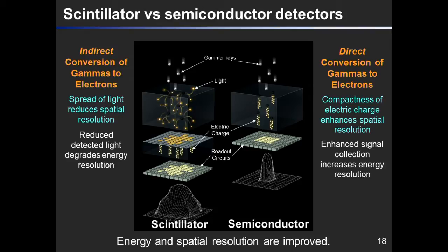On one surface of the scintillation material, we attach another device called a light sensing device. The light sensing device can be a photomultiplier a few inches in size. And recently a new one has come in, like a silicon-based photomultiplier. That one can be a few millimeters in size, very small. So this device will convert light into electrical signals, and then the signal will be processed by the readout electronics.